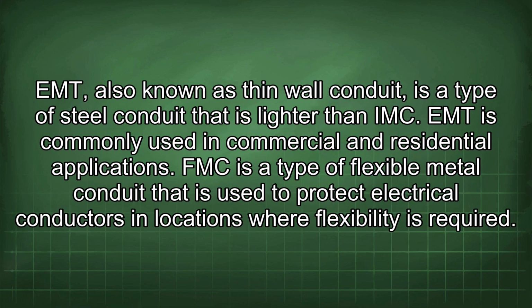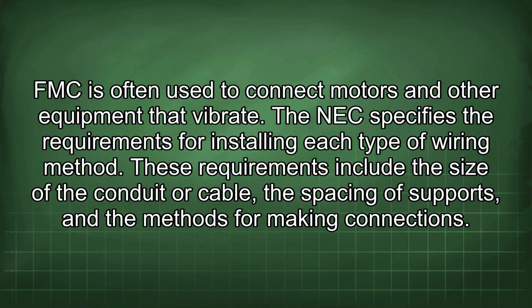EMT, also known as thin wall conduit, is a type of steel conduit that is lighter than IMC. EMT is commonly used in commercial and residential applications. FMC is a type of flexible metal conduit that is used to protect electrical conductors in locations where flexibility is required. FMC is often used to connect motors and other equipment that vibrate. The NEC specifies the requirements for installing each type of wiring method. These requirements include the size of the conduit or cable, the spacing of supports, and the methods for making connections.